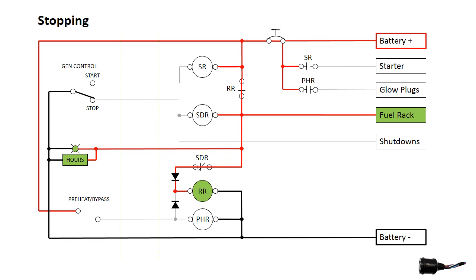Activating the stop circuit energizes the shutdown relay coil, which opens the run relay latching circuit, and de-energizes the run relay coil. The run relay contacts open and remove power from the ignition circuit.